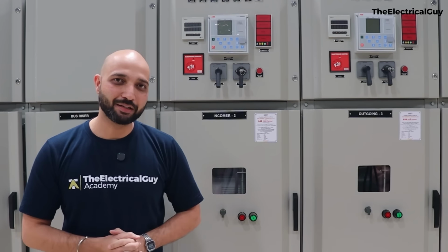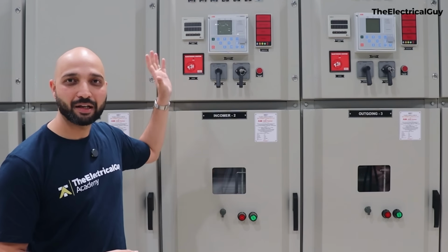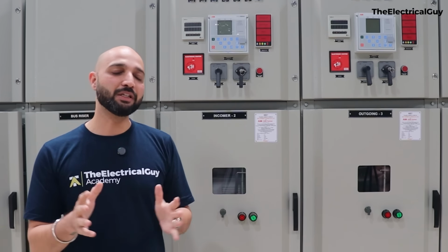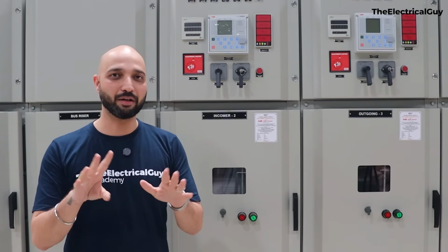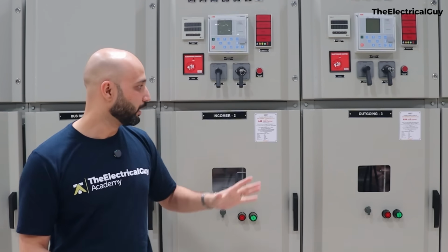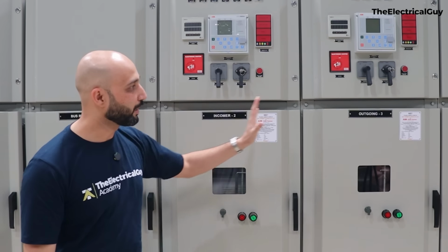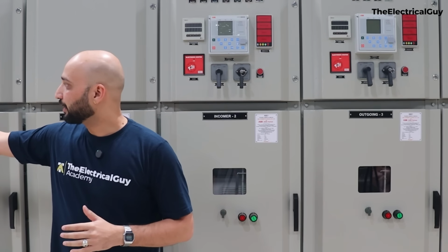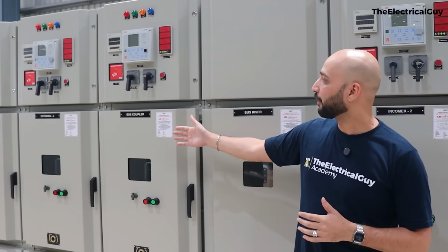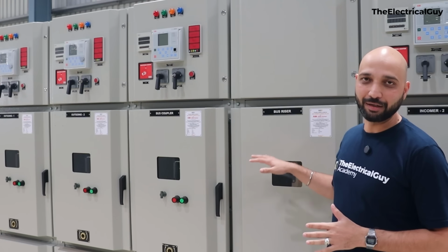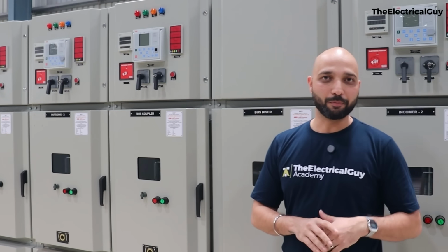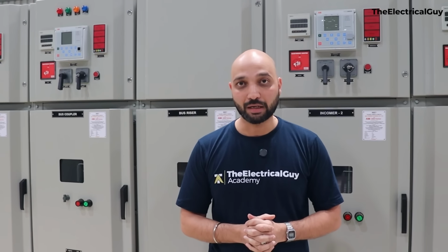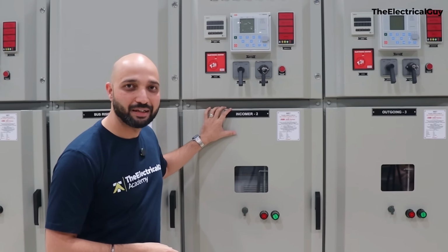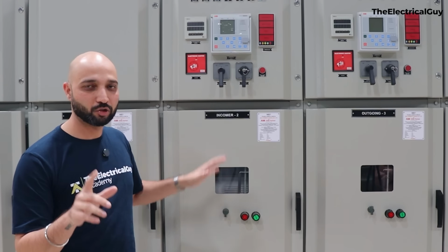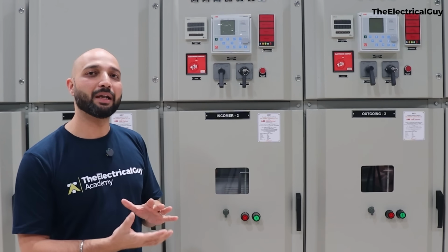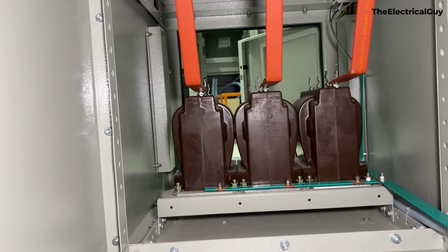So we are back at the panels and I am going to talk about what is inside and how these panels are arranged. Now as we have seen in the SLD, we had two incomers and every incomer had two outgoings. So you can see this is our incomer 2 and then we have two outgoings there, and there we have incomer 1, two outgoings, and then we also have bus coupler and bus riser panel. I'll talk about these two later when we explain all the panels. Now first let's start with what is there inside the incomer panel. Now if you remember, we saw the first thing was the cable entering into that, which you can see at the back side of the panel.